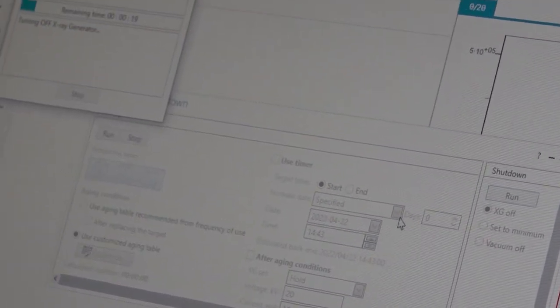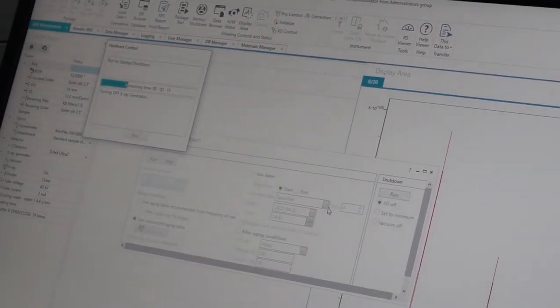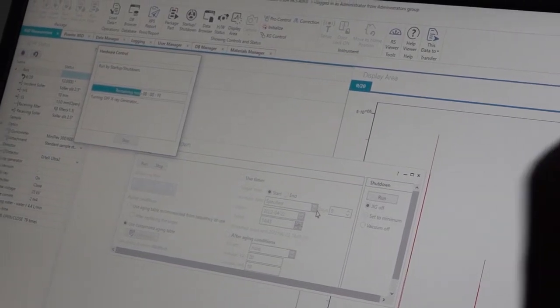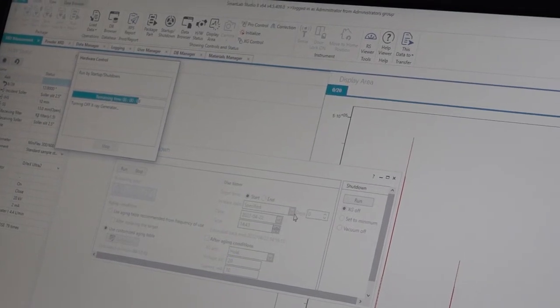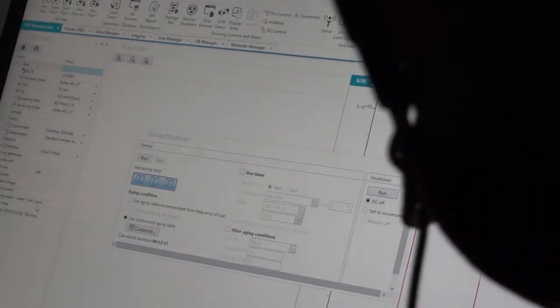It will ask you to shut down. You say yes, then the X-ray will switch off, and the chiller will be on only up to 3 minutes. Now the X-ray is on, but the flow is showing 4.4 only. The chiller will stay on because it will be hot now. It should cool. So for 3-4 minutes that water circulation will be there.